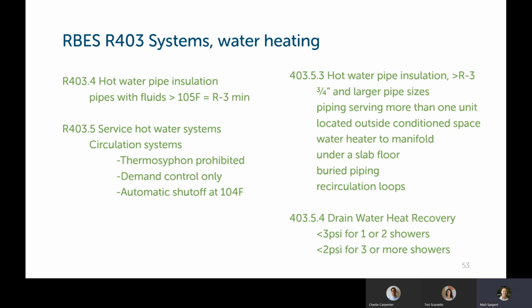So there's some water heating provisions in R403. Here, the hot water pipe insulation is required on pipes with fluids containing temperatures above 105 degrees Fahrenheit. That needs to be an R3 minimum pipe insulation. Service hot water circulation systems, the thermal siphon systems, are prohibited. Demand control only, and the automatic shutoff at 104 degrees Fahrenheit. So those are the provisions for recirculating systems.